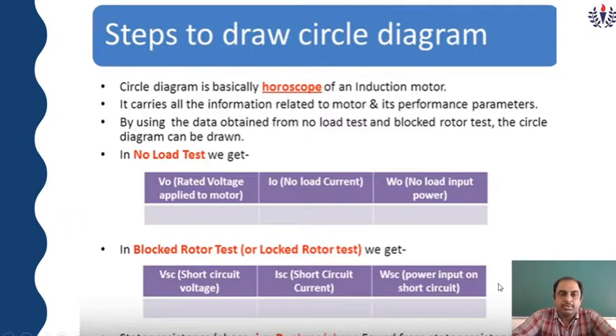Now by using this no load and blocked rotor data, we are going to plot the circle diagram. These are the steps to draw the circle diagram. The circle diagram is basically the horoscope of an induction motor. It carries all the information related to the motor and its performance parameters. To draw it, we already obtained the data from the no load and blocked rotor tests: V0, I0, W0, and in the blocked rotor test VSC, ISC and WSC, and the resistance value is also calculated.